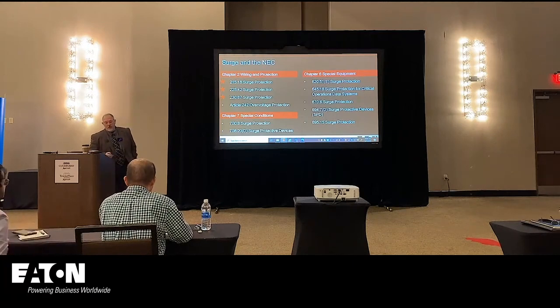All right, so we expanded surge, and again, 215, 225, and 230, and we went beyond dwelling units to other commercial type facilities. We went to dormitory units, guest rooms and guest suites of hotels and motels, and then nursing homes and limited care facilities used exclusively as patient sleeping rooms. Anybody do healthcare in the room?